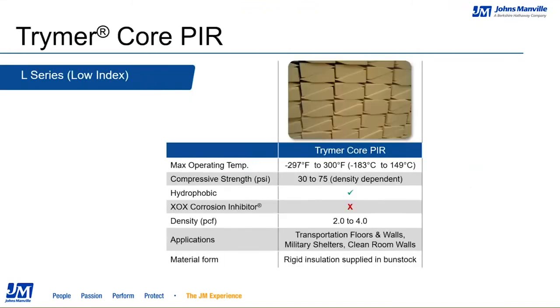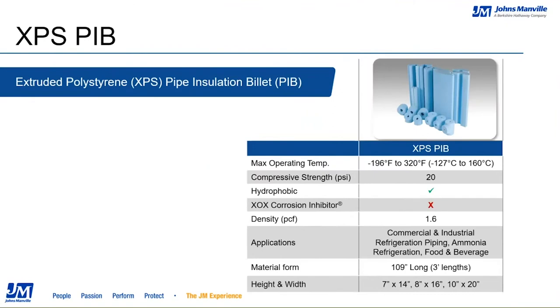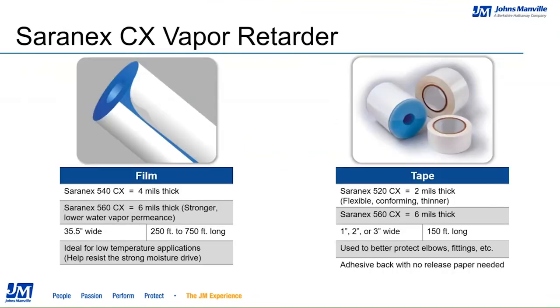The Trymer Core PIR — also known as the L series or low index series — has the same temperature range as the standard Trymer PIR. Compressive strengths range from 30 to 75 PSI based on densities of 2 to 4 lb. Applications include transportation, military shelters, and clean room walls. The L series exists because it is less dusty and has better flexural strength than the standard Trymer PIR products. The XPS PIB (extruded polystyrene billet) is ASTM C578 compliant with a temperature range of -196°F to 320°F, 20 PSI compressive strength, 1.6 lb density, and is often used in food and beverage refrigeration.